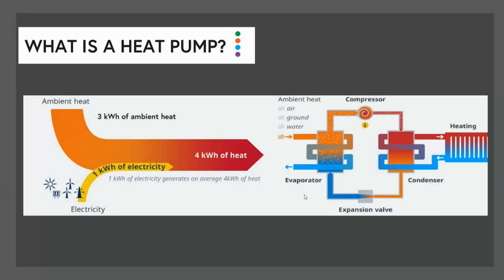So the evaporator is out in the air, and the one thing you can't see on this diagram is the fan. There is always a fan on an evaporator outside, and it blows a lot of air across the coil. Now, the way that the refrigerant absorbs energy is due to its boiling point. All refrigerants boil at different temperatures. So let's just pick R290 because that's kind of the topic of today. R290 boils at about -43 degrees, if my memory serves me. What that means is that it doesn't take very warm air to make that refrigerant boil and release its vapor, and therefore transfer heat to the system. As you boil a liquid fluid, that phase change releases energy, and that energy is taken away as part of the vapor that's expelled from the boiling of the liquid.